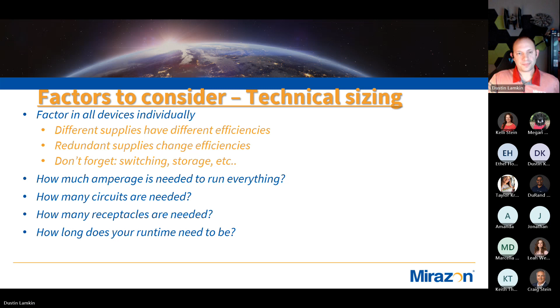Make sure you check the loads on your UPSs. You plugged it in a year ago and everything was fine, you were at 60% load. Well, Bob and Frank have been in here and plugged in some other stuff, and now you're at 80-90% load, so your runtime is way down from what it used to be. We definitely need to pay attention to that future load and capacity.